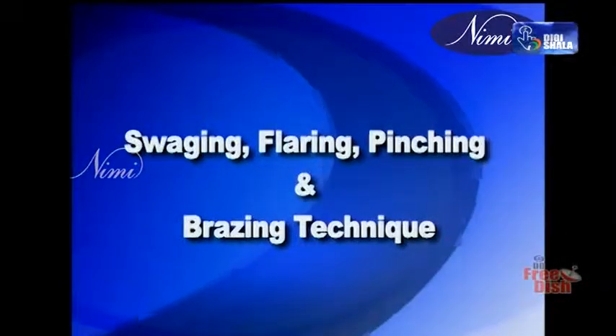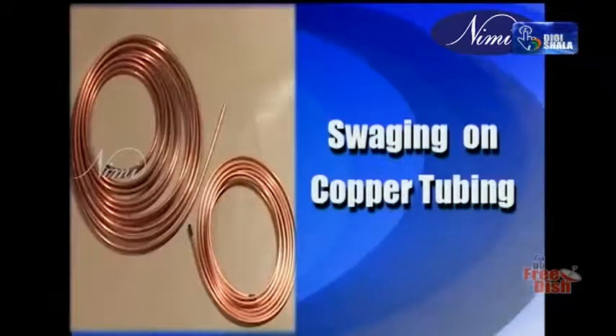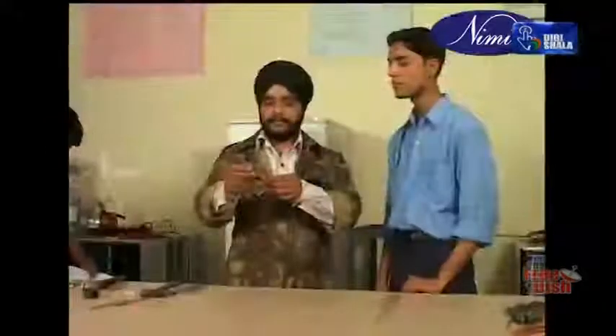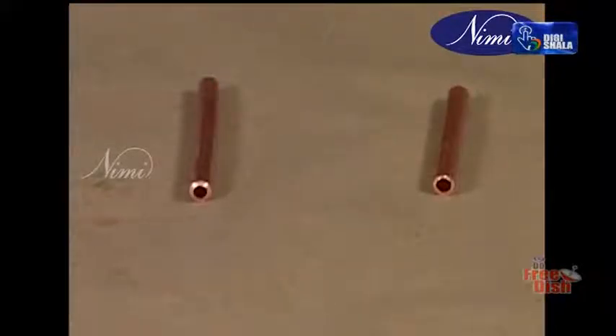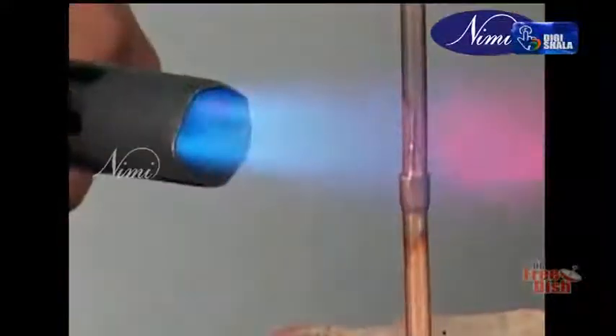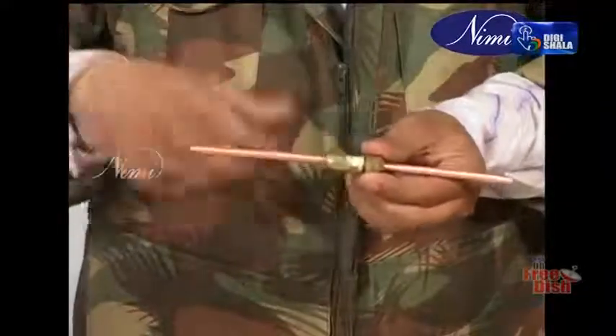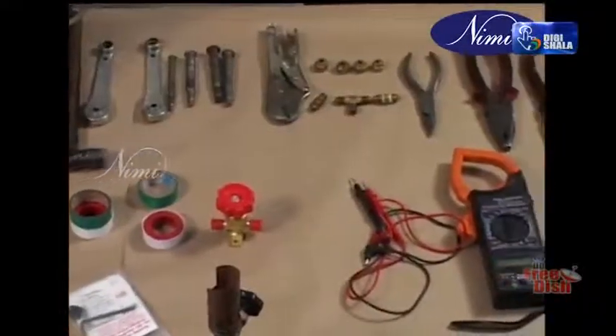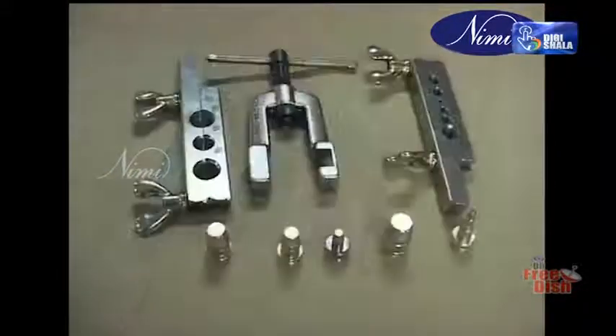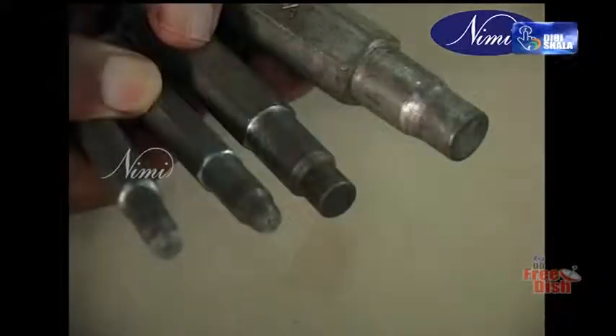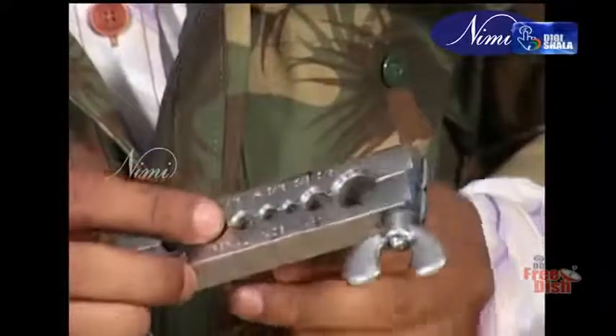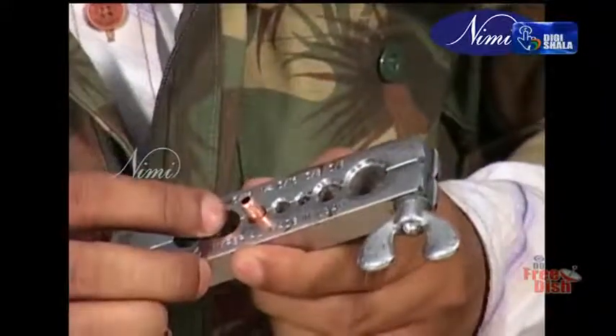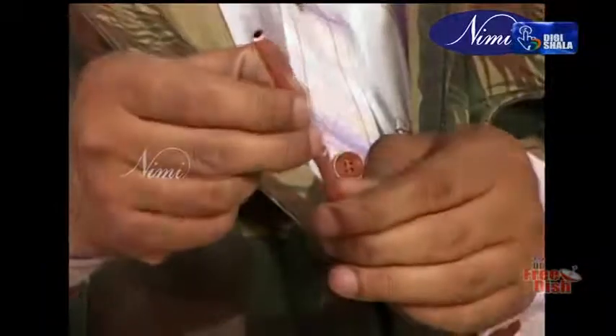Swedging, flaring, pinching up and brazing technique. Swedging on copper tubing. Swedging permits 2 pieces of soft copper tubing of the same diameter to be joined together without the use of fittings. It is more convenient to solder one joint than make 2 flare connections. 2 types of swedging tools are commonly used: punch type and screw type. When the punch type is used, the copper tubing is inserted into the correct hole size in the flaring block. Then a punch is inserted into the copper tubing and hammered down until it has entered the tubing the desired distance.